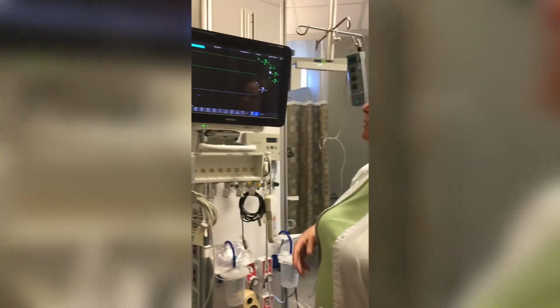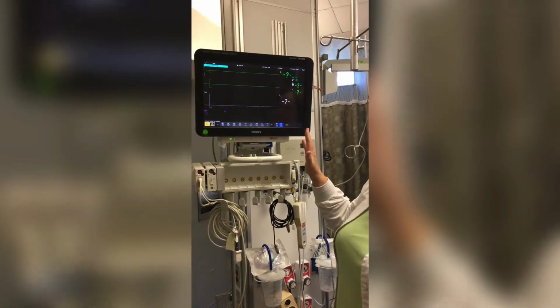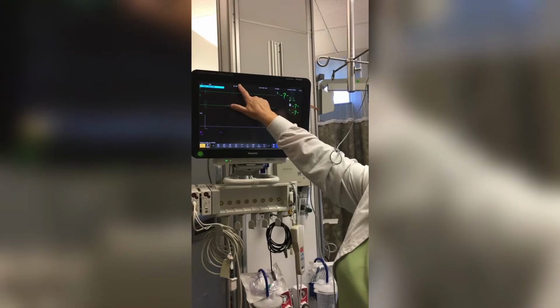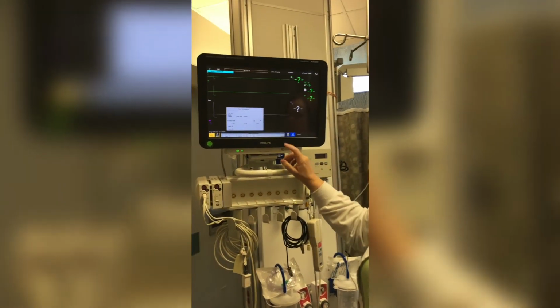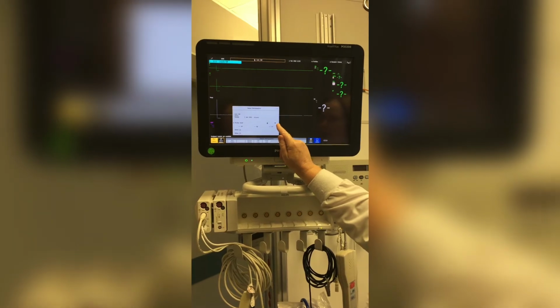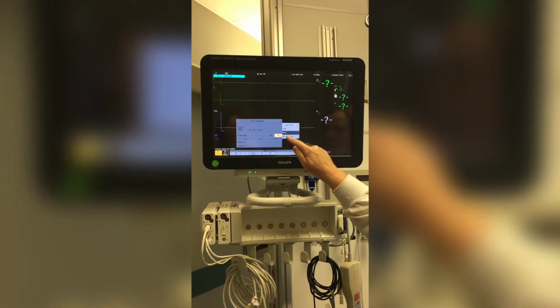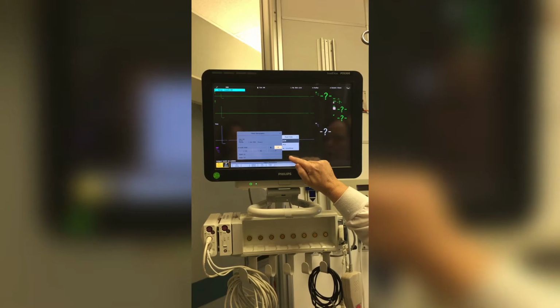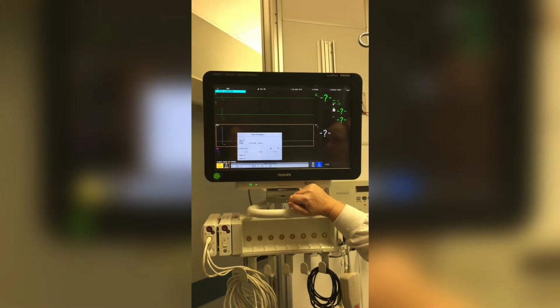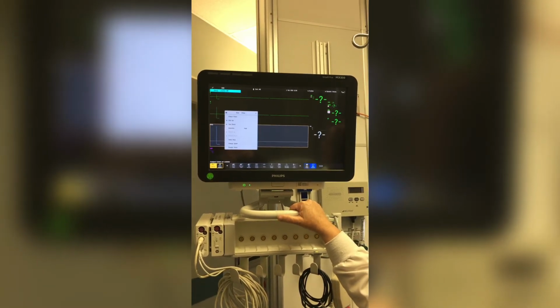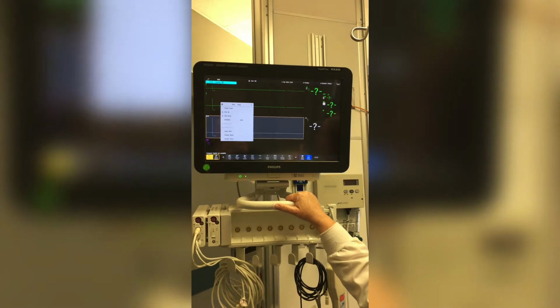So let's go to the monitor. How are we going to turn this on so this monitor will know that the patient is pacing? You're going to go to the patient's name at the top and click on the patient demographics. Over here to the far right, there's a little heart, so you're going to push the heart. It says pace mode, on or off. You put the pacemaker on. Now that it's on, the monitor will read the pacemaker as being in normal rhythm for this patient. You can also do it at the main nurse's station if you don't do it in the room.